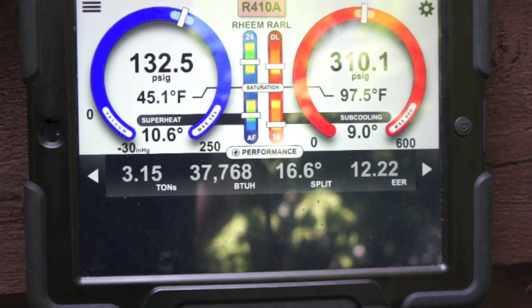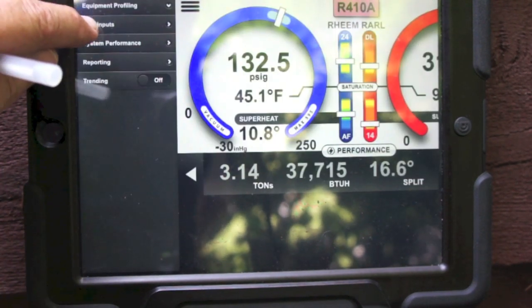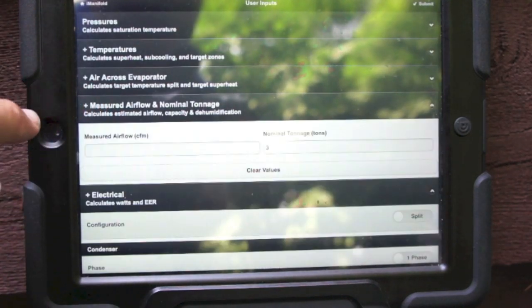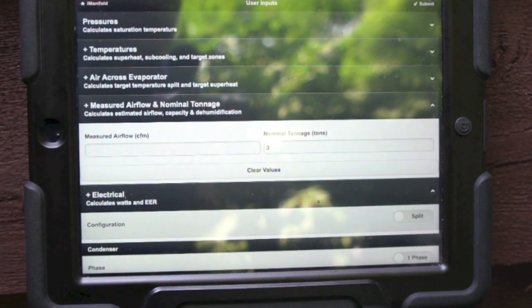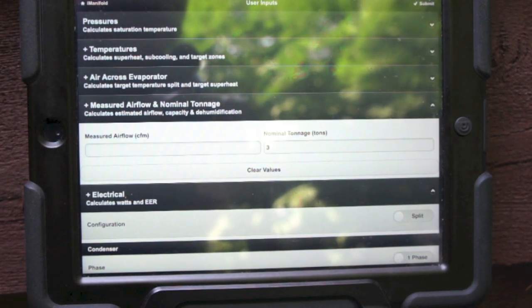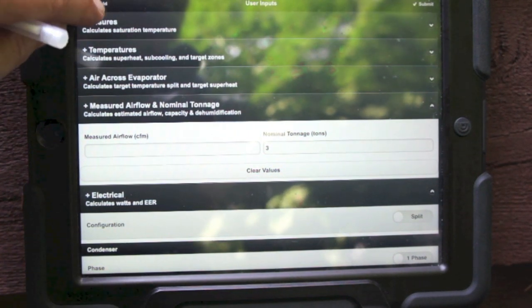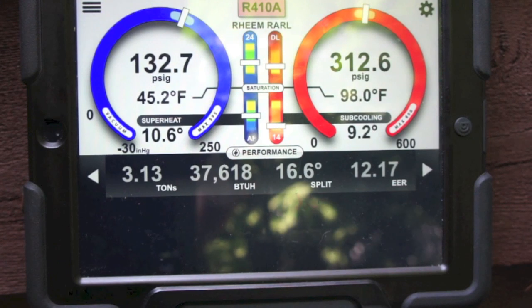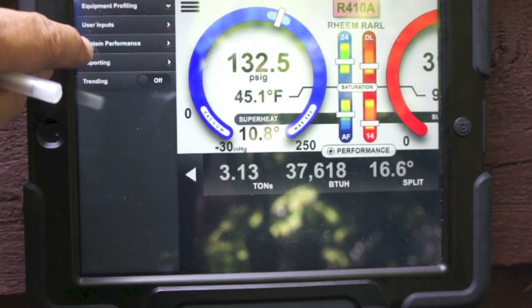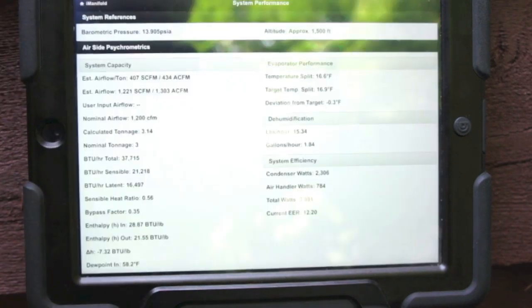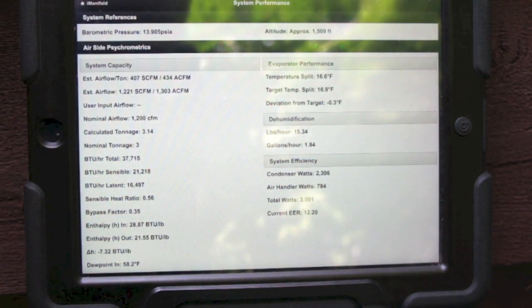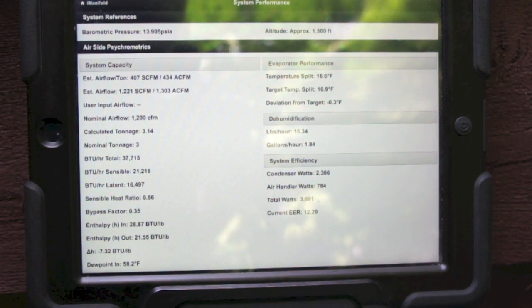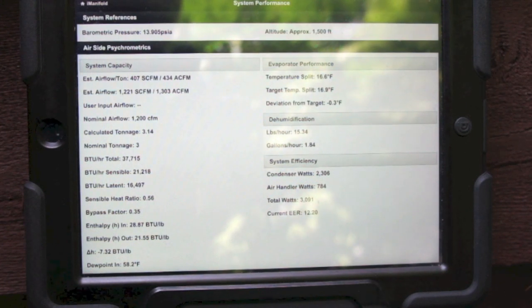We have tried this over and over again, and one of the challenges, and let me go back to user inputs for just a second. And you can enter a measured airflow. If you have an actual airflow, it will calculate based off the measured airflow in lieu of the estimated airflow. But here's the challenge. We've looked over and over and over again at trying to measure airflow, and it is such a tricky thing to do to get it accurate. The estimated airflow works off of the performance of the coil, and it is much easier to measure temperatures and humidities accurately than it is to measure the airflow in a lot of duct systems.